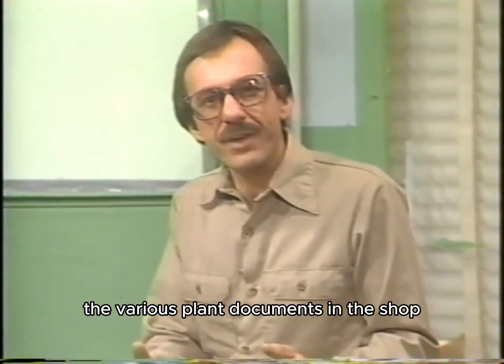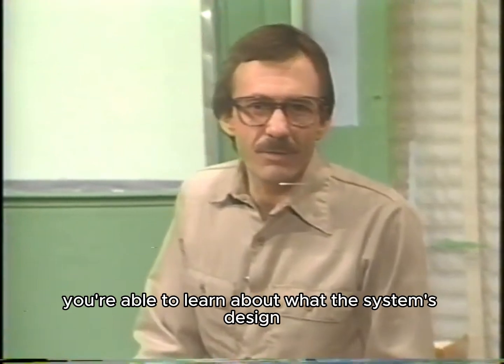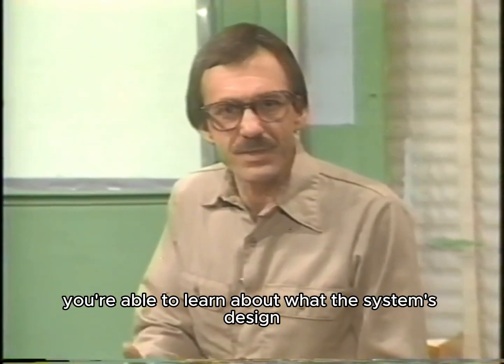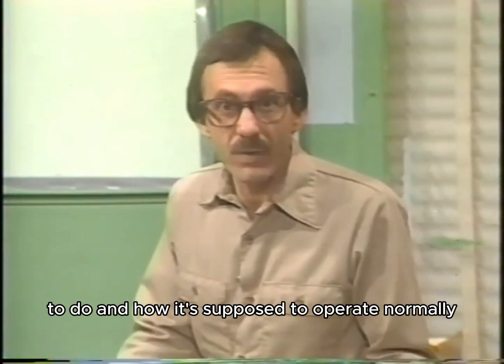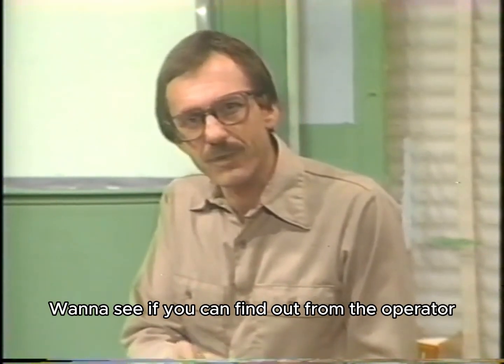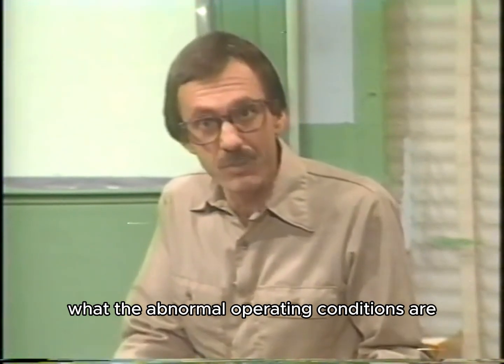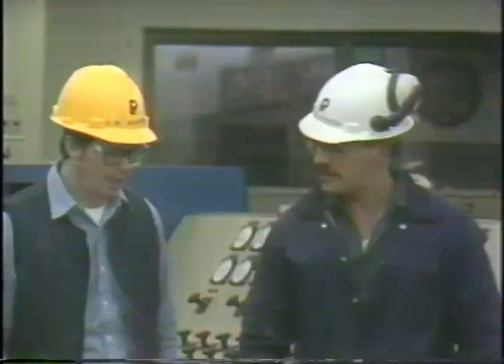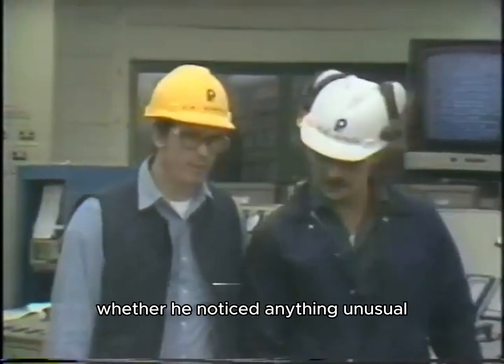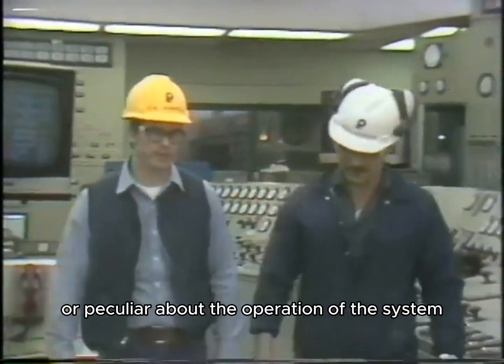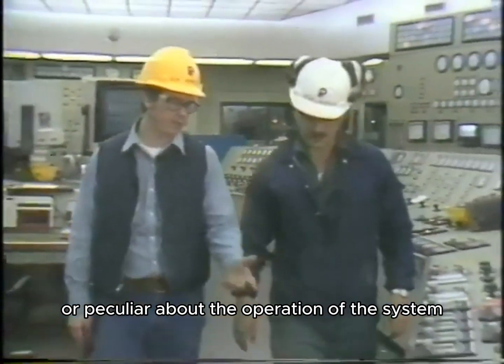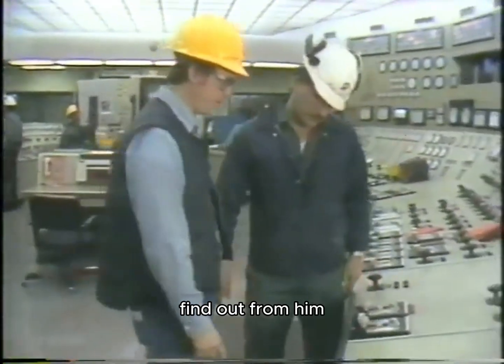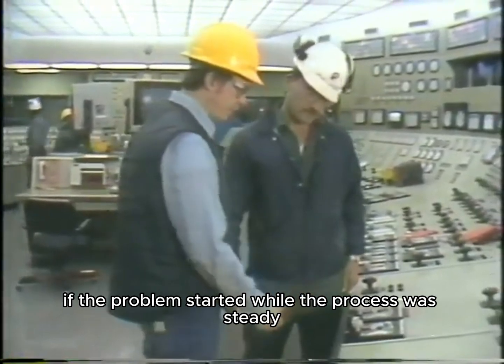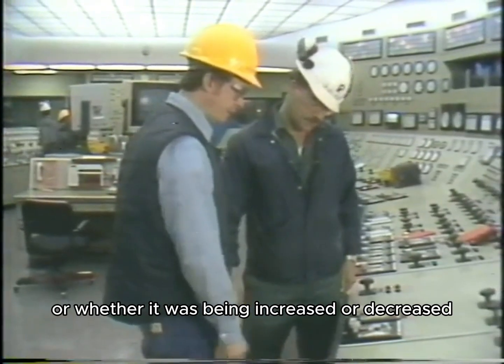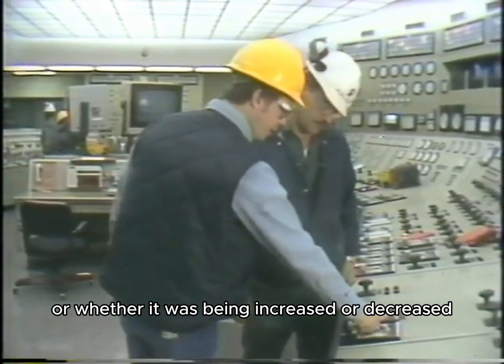While you were studying the various plant documents in the shop, you were able to learn about what the system's designed to do and how it's supposed to operate normally. Now see if you can find out from the operator what the abnormal operating conditions are. Ask him, for example, whether he noticed anything unusual or peculiar about the operation of the system. Find out from him if the problem started while the process was steady or whether it was being increased or decreased.